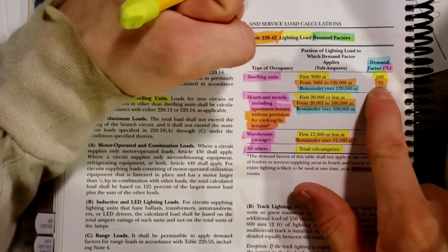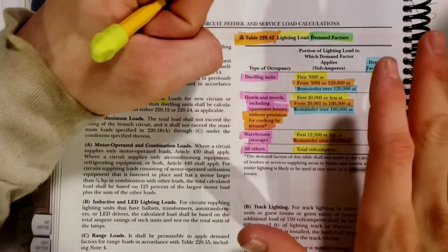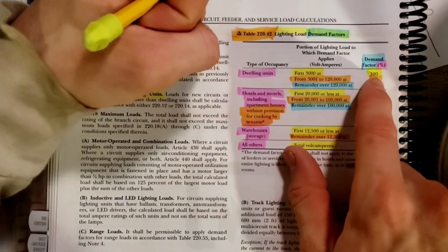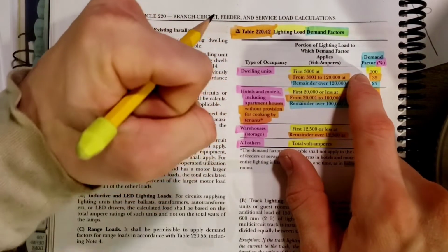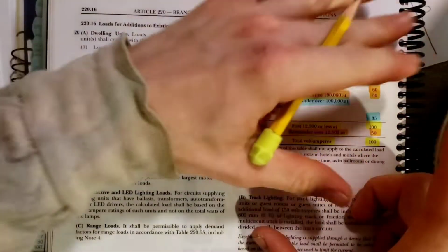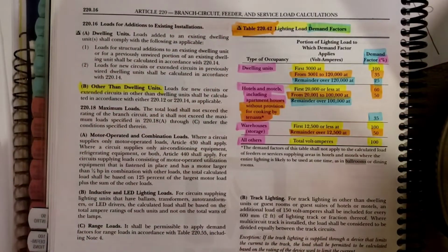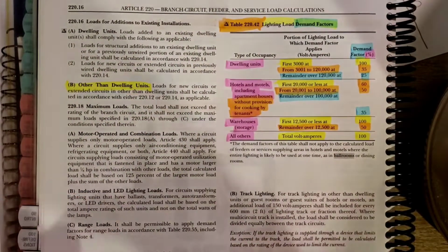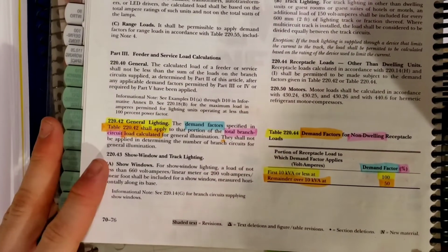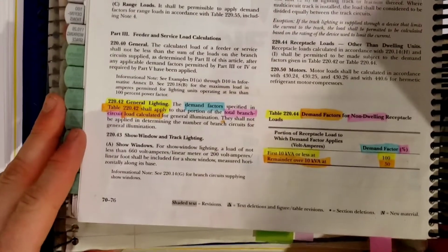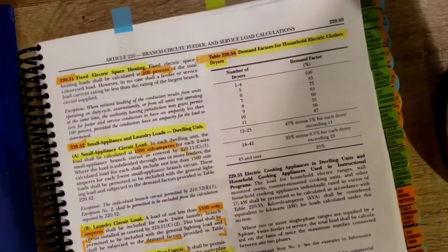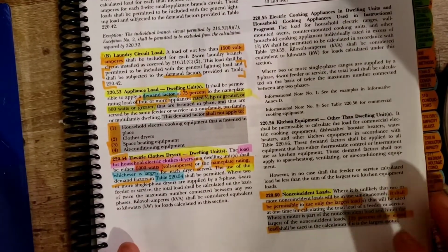So we took our remainder after taking away that 3,000. And we times that by 0.35. And then we get that answer. And since our first 3,000 is at 100%, that's why we simply take our 3,000 and we add it back at 100%. It's just a simple way of solving for this, okay? So it just helps you solve it quickly. By the way, we are on page 76 of the codebook. And if we just flip it on the next page, 77, we're here.